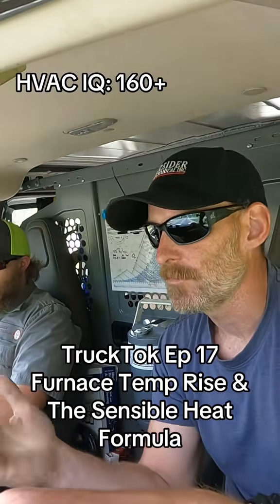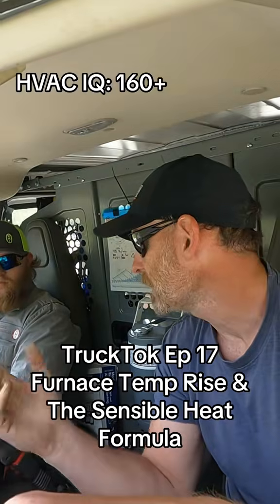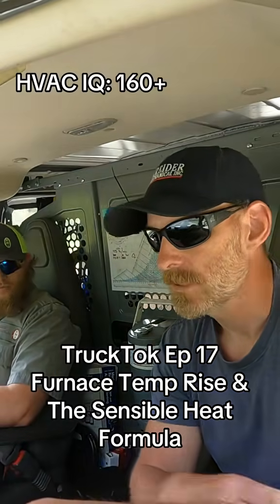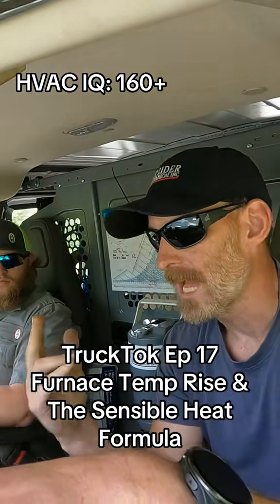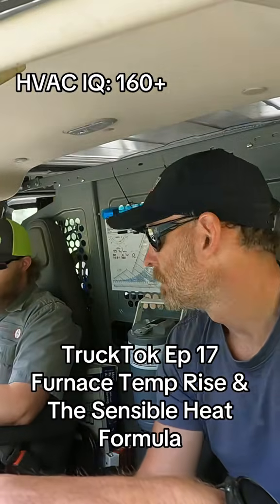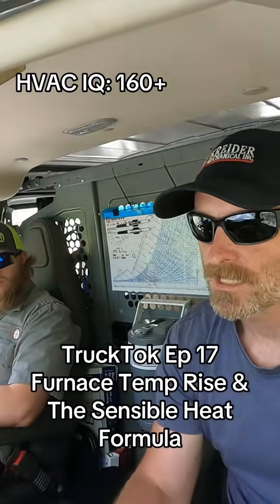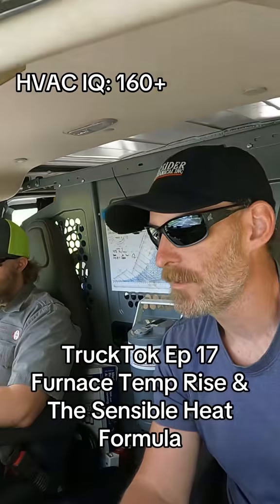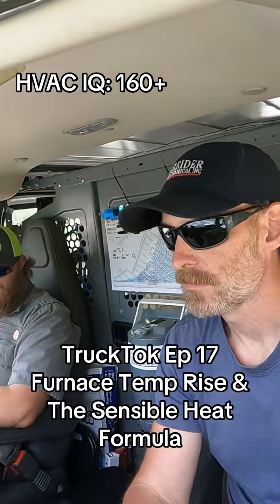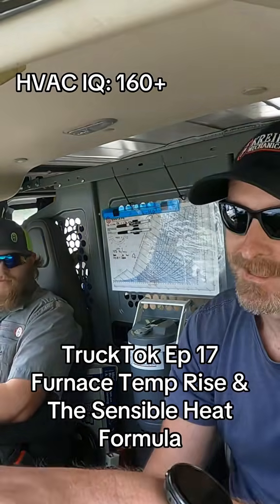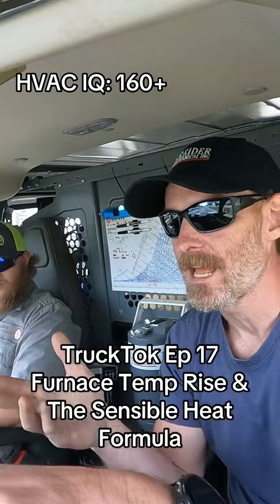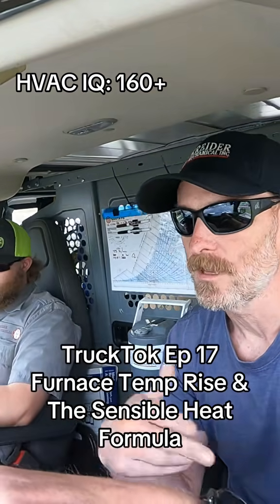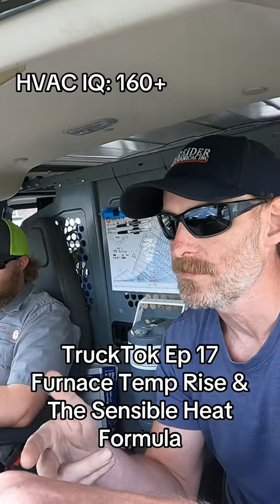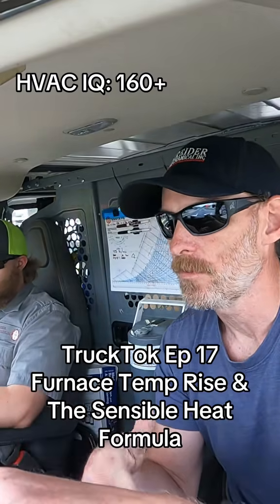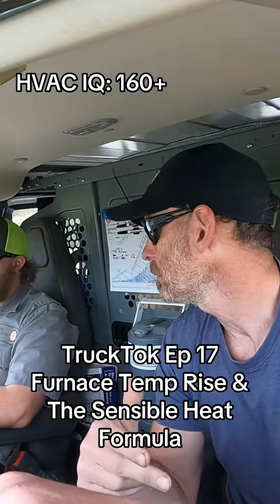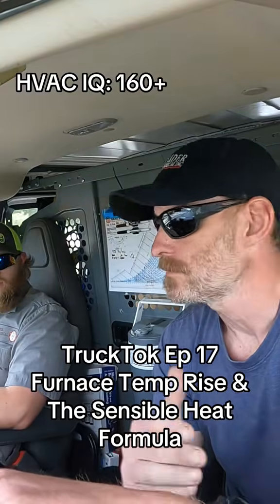Because that furnace had an input of 200,000 BTUs, but it was an 80% furnace, wasn't it? Yes. So how many BTUs was the output of that furnace? It would be 160,000. Yeah, it was 160,000 BTU output. Where'd that other 40,000 BTUs go? Out the flue. Damn right it went out the flue. Anyway, them engineers, they figured that out and they put that on that nameplate so a bunch of knuckleheads like us that ain't got flow hoods and pitot tubes and can't find the blower chart because the manufacturer don't give it out freely can make sure that furnace don't fail.